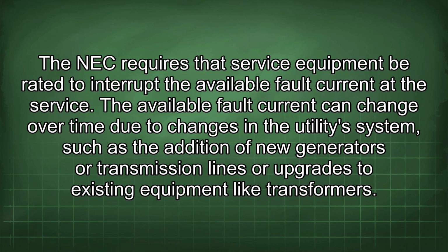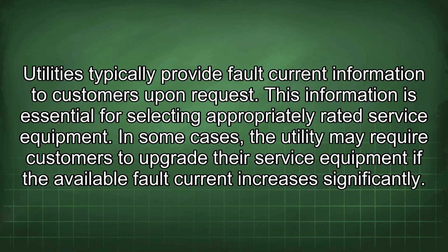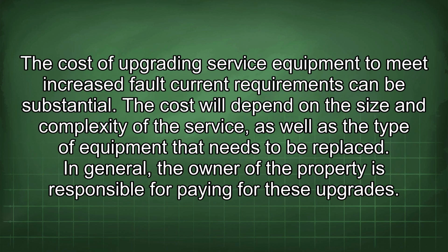The available fault current can change over time due to changes in the utility system, such as the addition of new generators or transmission lines, or upgrades to existing equipment like transformers. Utilities typically provide fault current information to customers upon request. This information is essential for selecting appropriately rated service equipment. In some cases, the utility may require customers to upgrade their service equipment if the available fault current increases significantly. The cost of upgrading service equipment to meet increased fault current requirements can be substantial.